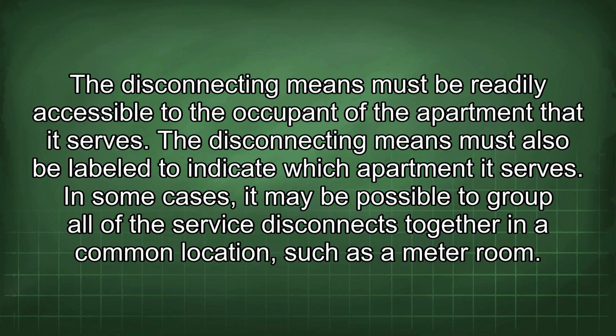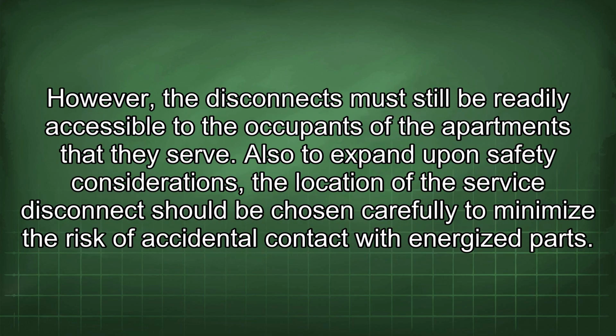In some cases, it may be possible to group all of the service disconnects together in a common location, such as a meter room. However, the disconnects must still be readily accessible to the occupants of the apartments that they serve.